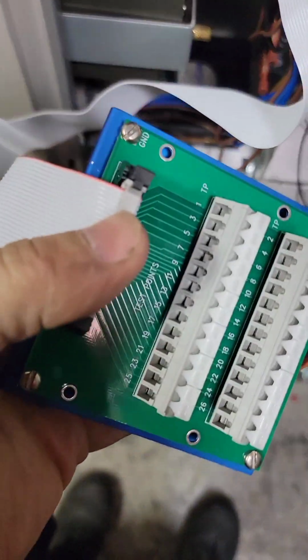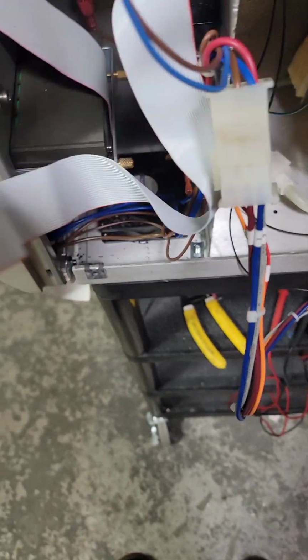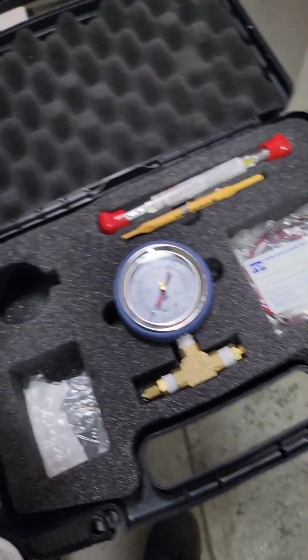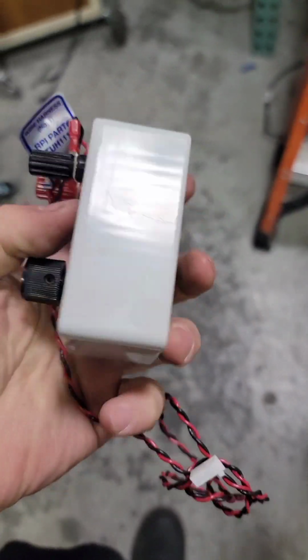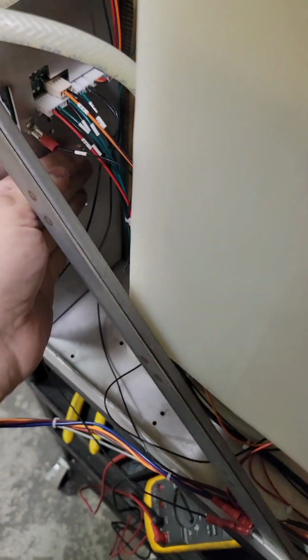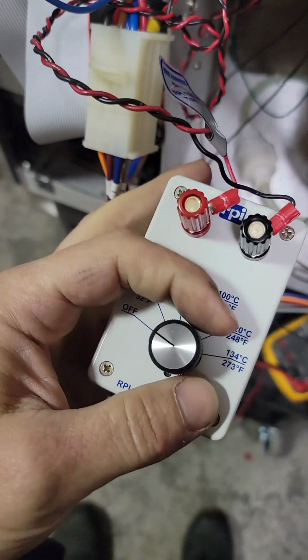Whatever. This is your little board, your test point board. It's going to plug in right here. And the purpose of this is, it's a lot easier to plug your leads from your multimeter into these test points than it would be trying to hold it on the different pins and different components. So, to make that easy for you. And if you're going to do a temperature calibration, you need what's called a PT100. This is just a box full of resistors. Because if you know anything about how thermometers work, you would understand that all it's doing is reading different resistances that are programmed into the board. It knows that this resistance, this is my temperature, this resistance, this is the temperature, yada yada yada. So this little box does that for you.